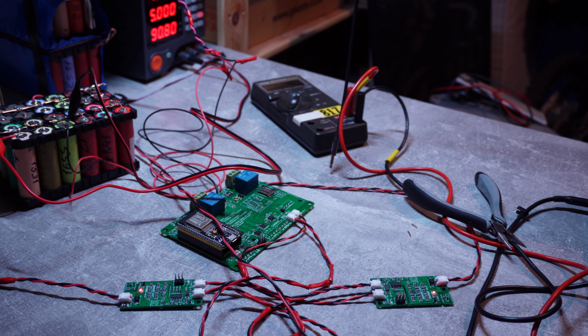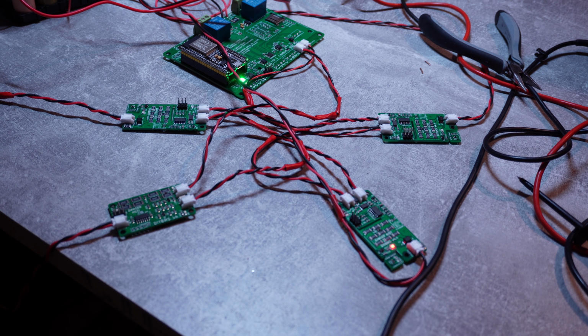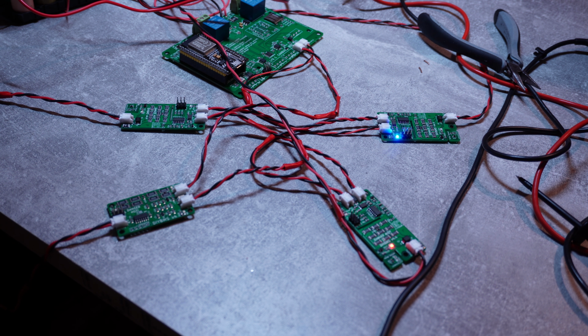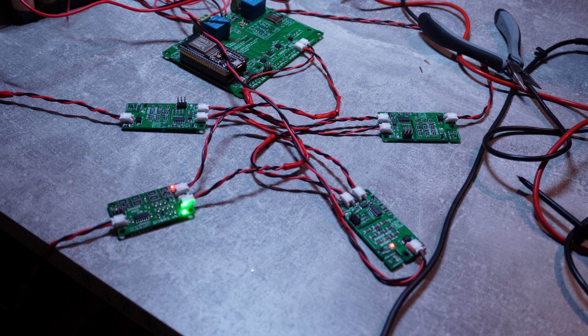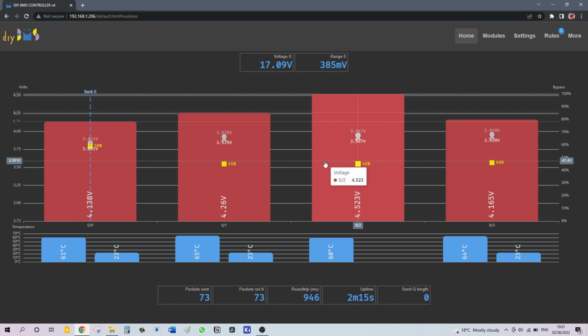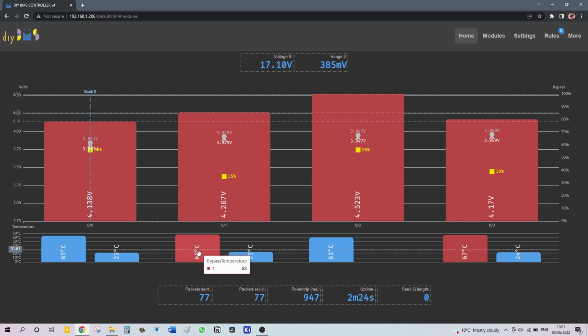Each module doing the balancing was illuminating a red LED. As DIY BMS was constantly balancing those cells, the temperature very quickly reached the limit of 66 degrees C, which resulted in that particular cell going into bypass mode.